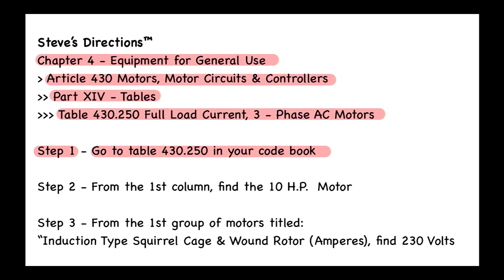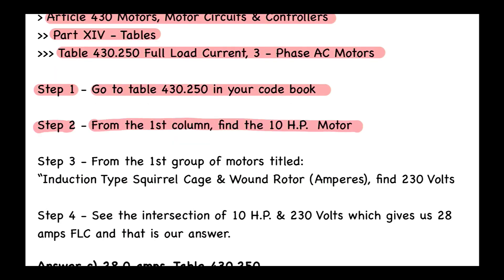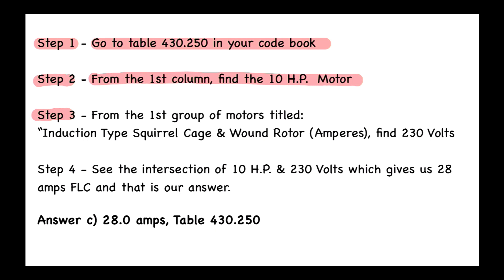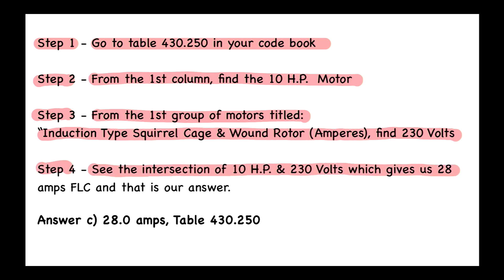Let's go back to the textbook and review how we solved this. Step two: from the first column, find the 10 horsepower motor. Step three: from the first group titled 'induction type squirrel cage and wound rotor amperes,' find 230 volts. Step four: the intersection of 10 horsepower and 230 volts gives us 28 amps FLC. The answer is C — 28 amps — and the code reference is Table 430.250.